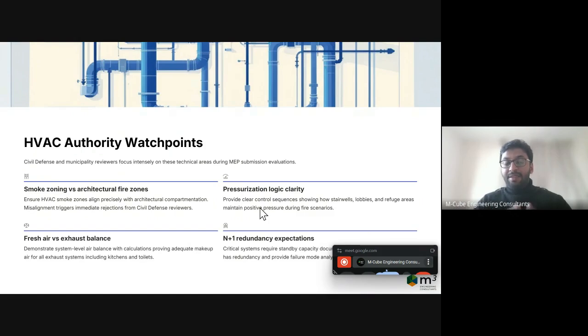The second thing is related to fresh air and exhaust balancing. Generally when doing the design, the calculations are correct, but on the drawing, the flats or apartments end up negatively pressurized, because the fresh air is calculated at a lower level, or the exhaust is more. So individual apartments or flats are generally negatively pressurized.